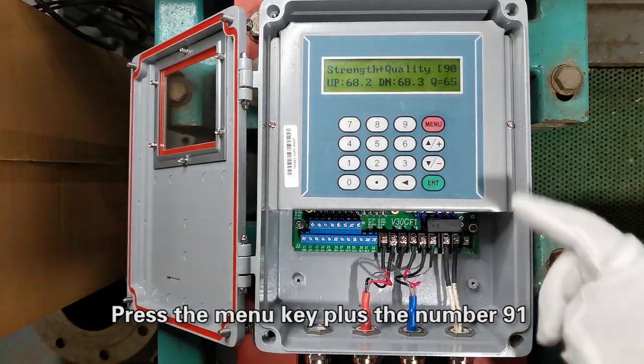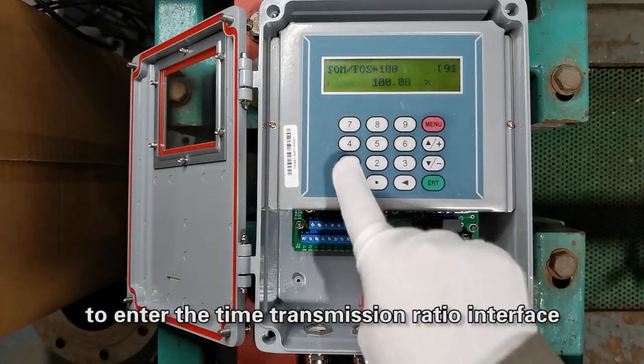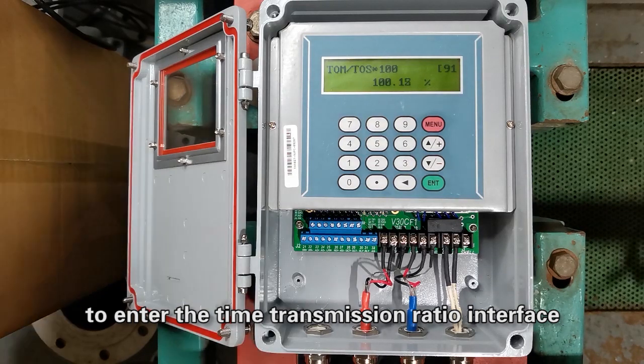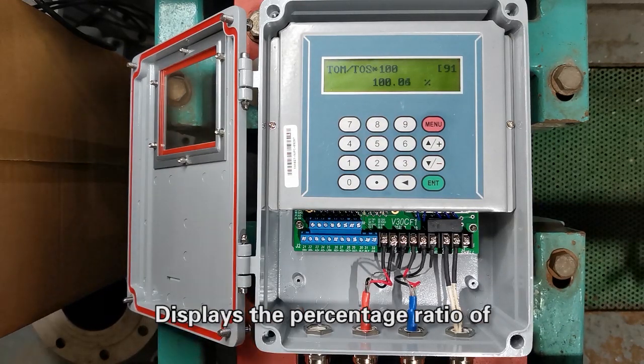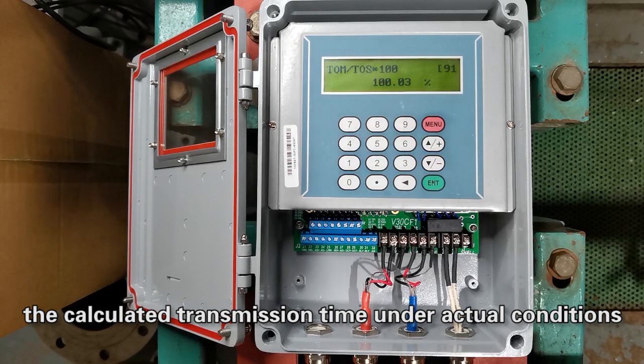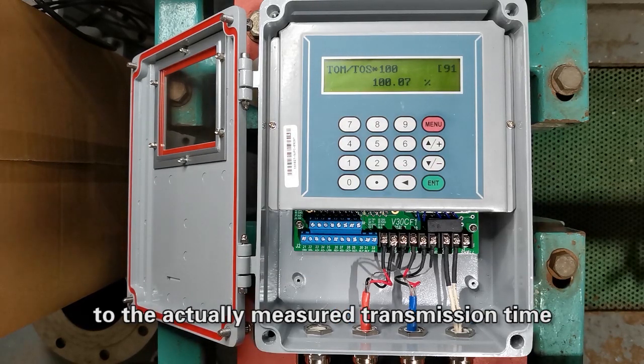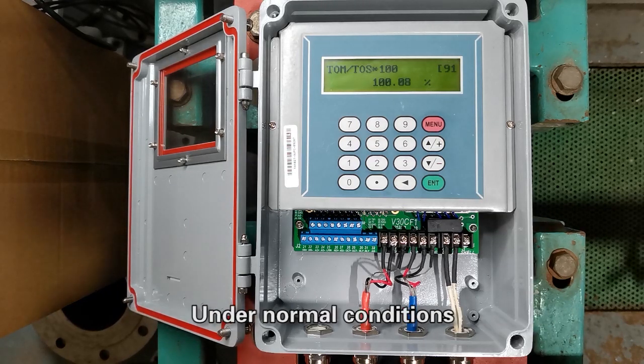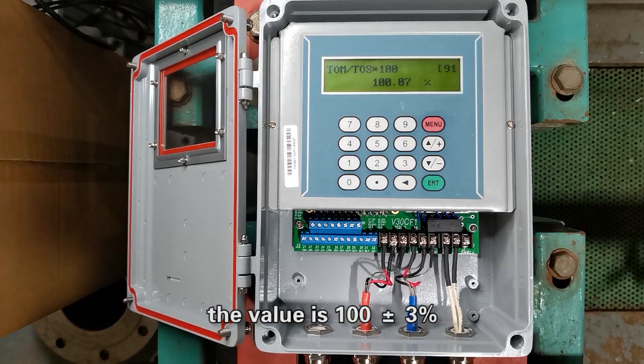Press the menu key plus the number 91 to enter the time transmission ratio interface. It displays the percentage ratio of the calculated transmission time under actual conditions to the actually measured transmission time. Under normal conditions, the value is 100 plus or minus 3%.